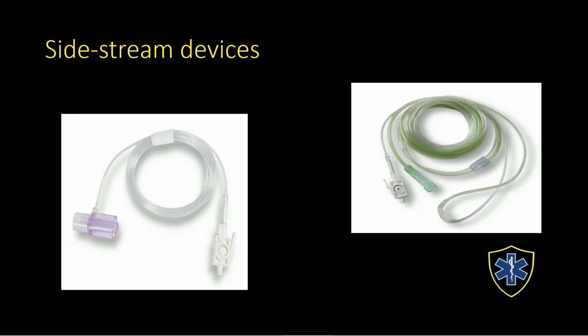Now, this will actually pull the patient's exhaust air or patient's exhalation back to the monitor and actually allow it to be read again by that pump. So we've got different devices, and the side stream can give us a lot more options. This one typically is one of the easier ones to use. One thing to remember, most side streams require calibration. However, the fact that we can use it with both breathing or intubated and non-intubated patients is a big plus for us.